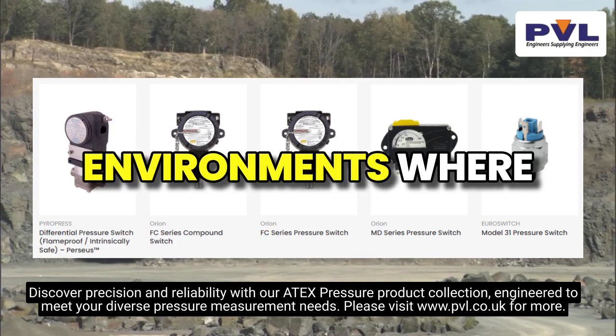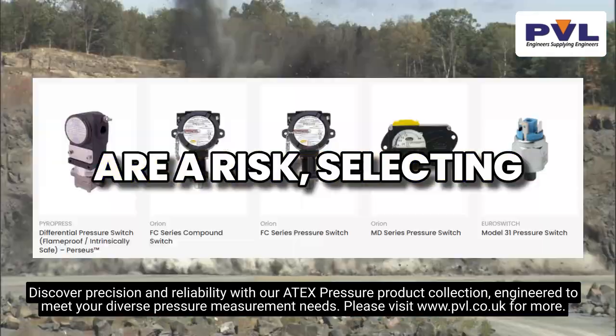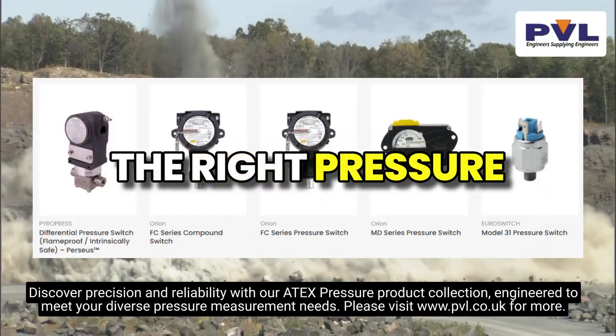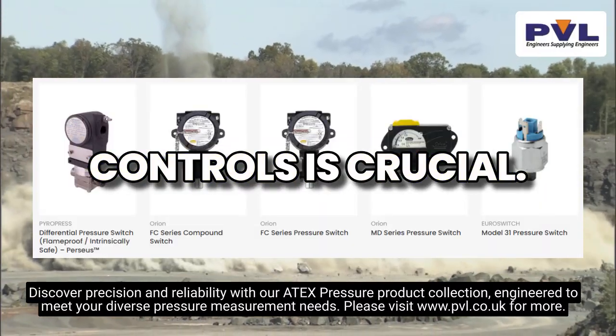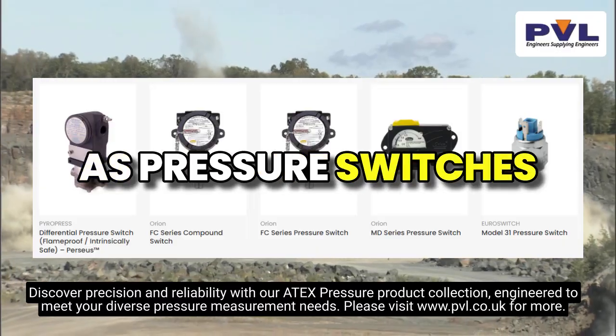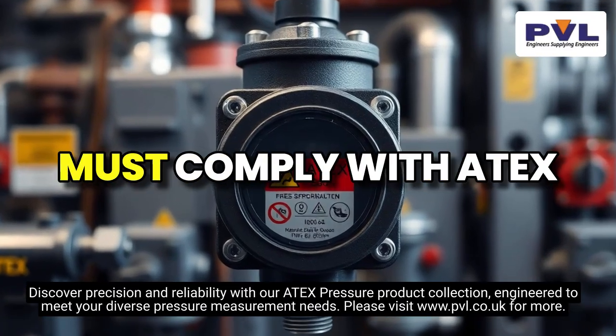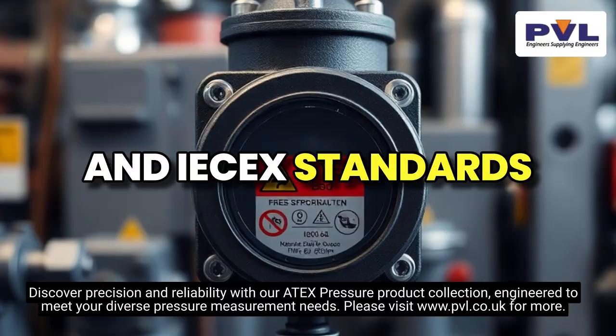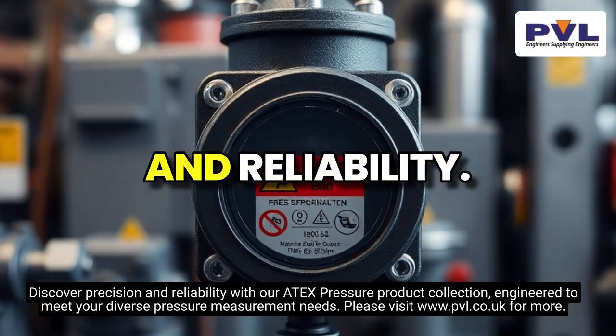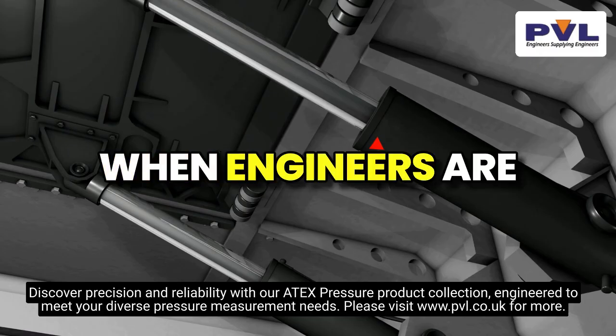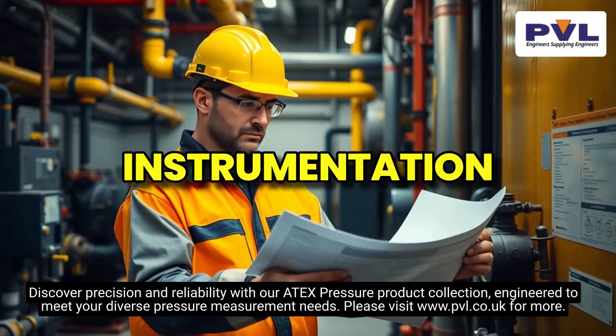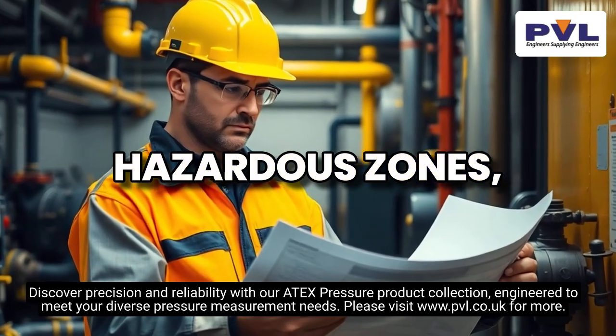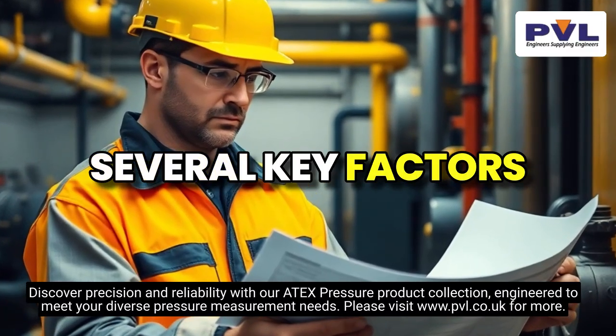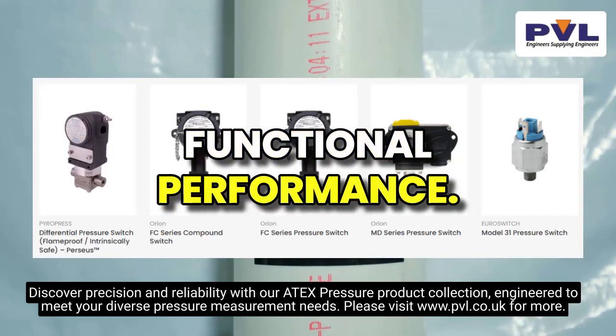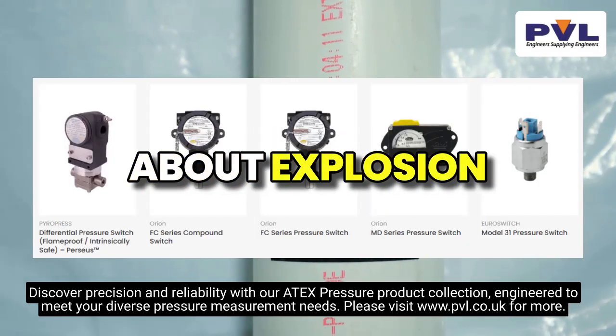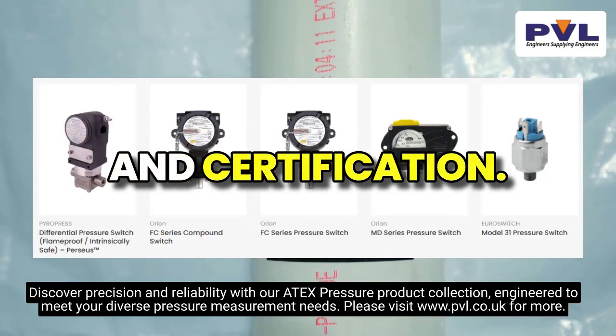In industrial environments where explosive atmospheres are a risk, selecting the right pressure controls is crucial. These devices, such as pressure switches and differential pressure controls, must comply with ATEX and IECEx standards to ensure safety and reliability. When engineers are tasked with specifying instrumentation for these hazardous zones, they need to consider several key factors beyond just functional performance. First, let's talk about explosion protection concepts and certification.